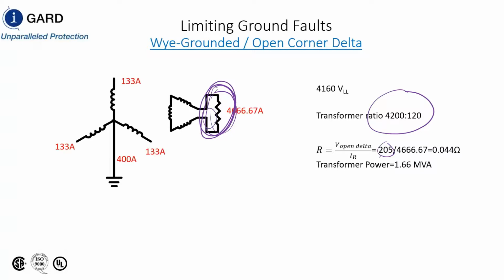But the amount of current going through that resistor is going to be a function of 133 amps. So basically 4,666 amps is flowing through that resistor. So 205 divided by 4,666 is 0.044 ohms. Now you need a 1.6 MVA transformer to take care of that.